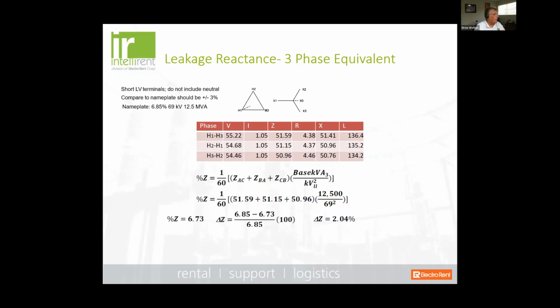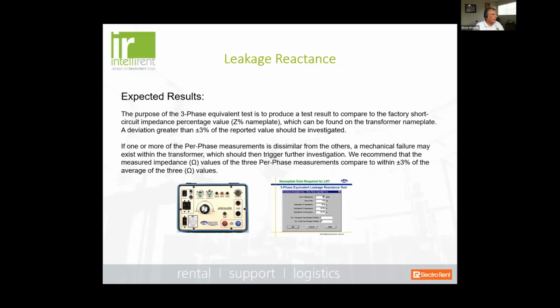Okay, so for a three-phase equivalent, you can see the formula here. I won't go into it in too much detail because I don't like math. But anyway, you can see here that based on the measurement, we get a measurement of 6.73, and basically your three-phase equivalent should be within plus or minus 3% of the nameplate rating of the transformer. Okay, 3%, that's our maximum allowable tolerance in the measured three-phase equivalent as opposed to the nameplate rating. Now the purpose of the three-phase equivalent is to produce test results to compare to the factory short circuit impedance. Okay, if one or more of the per phase measurements is dissimilar from the others, then a mechanical failure may exist within the transformer.